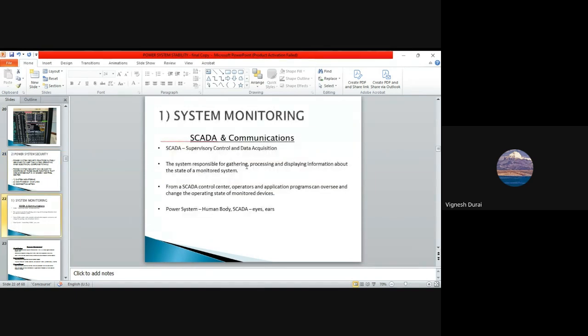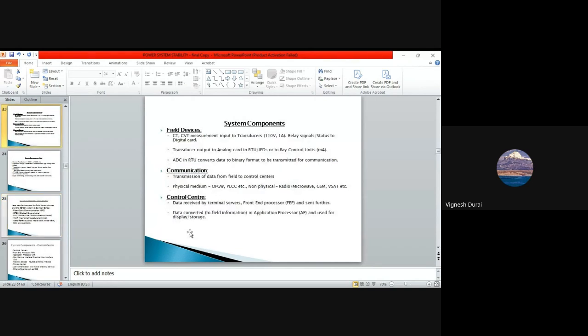For system monitoring purposes, we use SCADA. All of you would have seen all these things in workshops. At present we are using SCADA for our communication purpose. SCADA is like our sensors, and the power system is the human body. In system components, at field level, we have CTs and CVTs. They are the main things. They supply input to the transducer. The transducer gives analog output, which is fed into RTUs. The RTUs have an ADC, an analog to digital converter, and the RTUs convert and transmit through communication channels. In communication channels, we are using OPGW and PLCC communication.